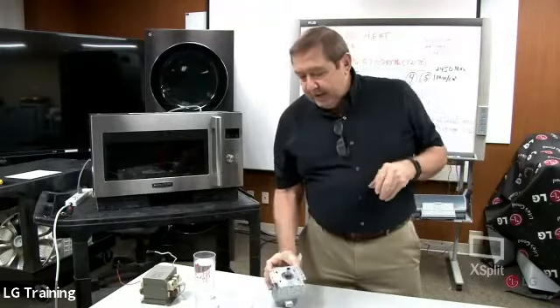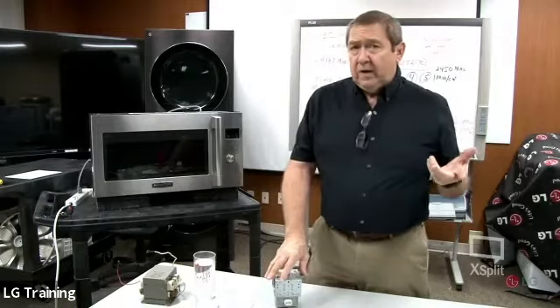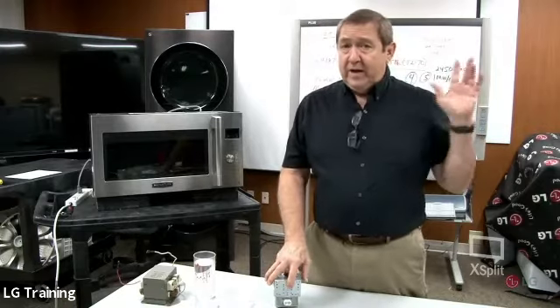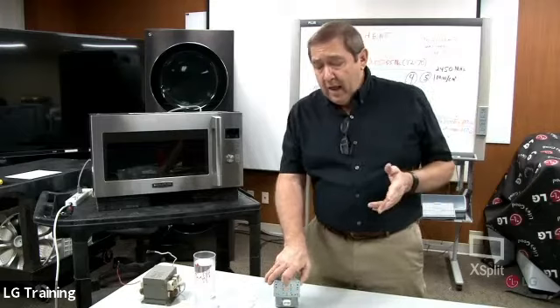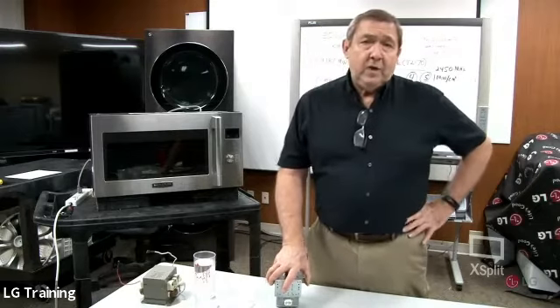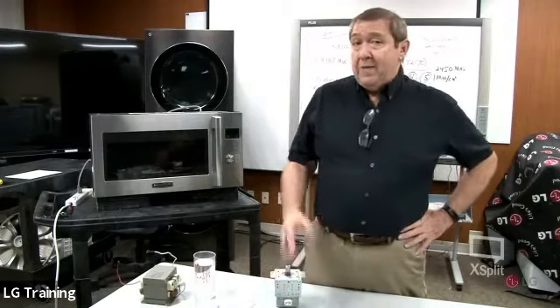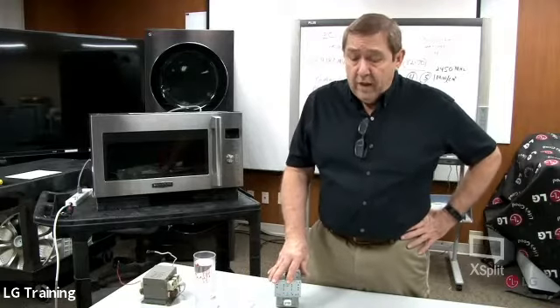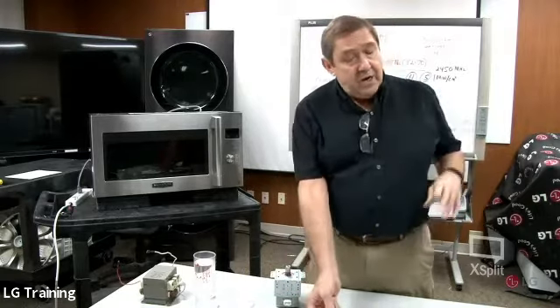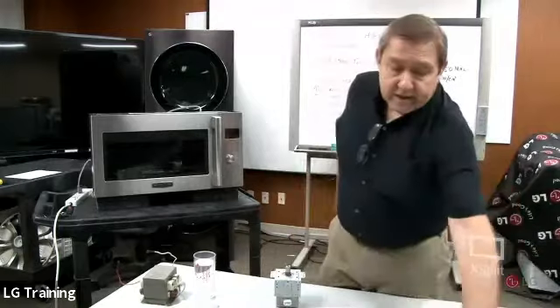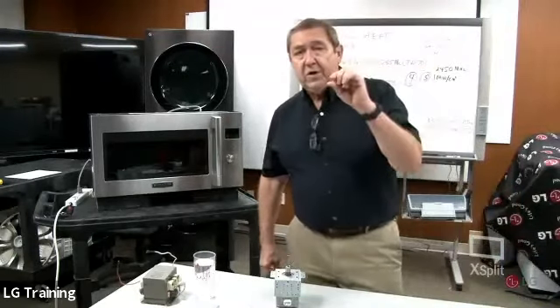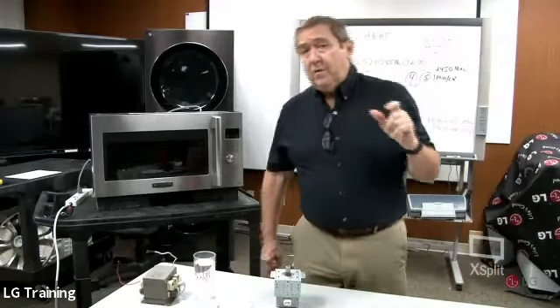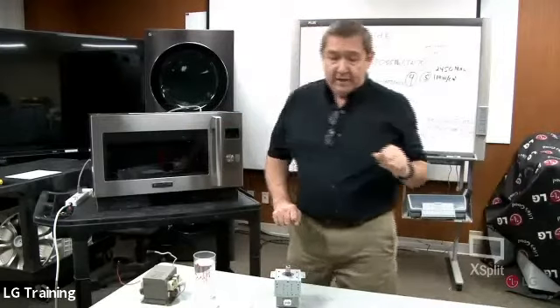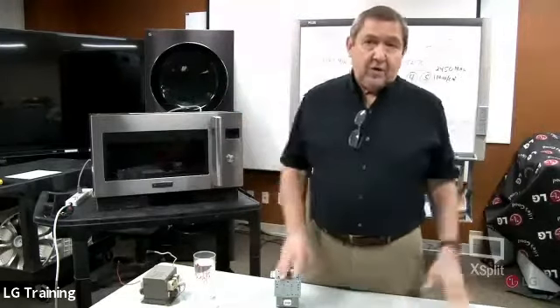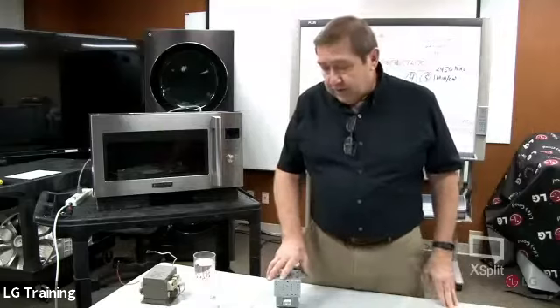But one of the things they didn't like customers doing with microwaves was cooking popcorn. We didn't have microwave popcorn back then, but customers would read little articles on how to make popcorn in the microwave. As manufacturers, we used to say no, you can't do that, because there was very little moisture inside those kernels, nothing to absorb the microwaves, and it could damage the magnetron. Now it's pretty much standard, it comes on all microwaves.